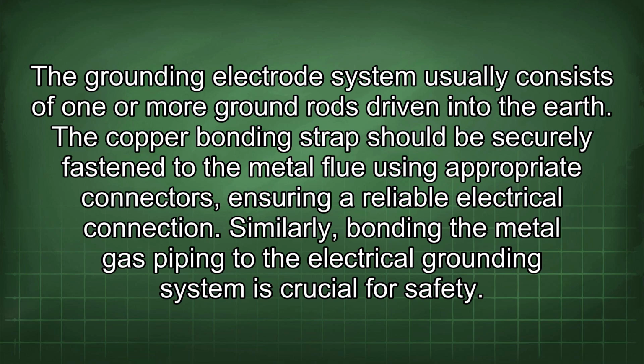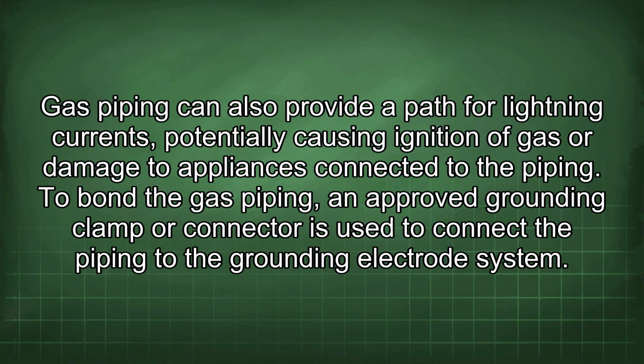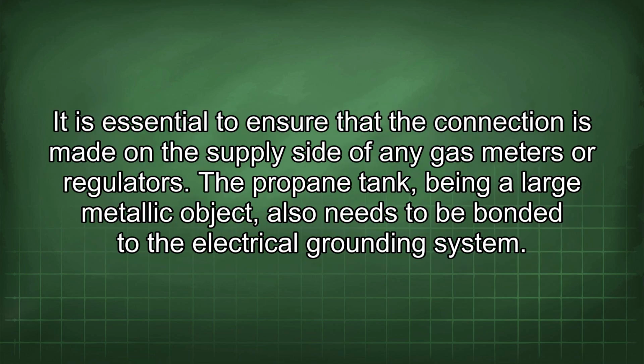Similarly, bonding the metal gas piping to the electrical grounding system is crucial for safety. Gas piping can also provide a path for lightning currents, potentially causing ignition of gas or damage to appliances connected to the piping. To bond the gas piping, an approved grounding clamp or connector is used to connect the piping to the grounding electrode system. It is essential to ensure that the connection is made on the supply side of any gas meters or regulators.